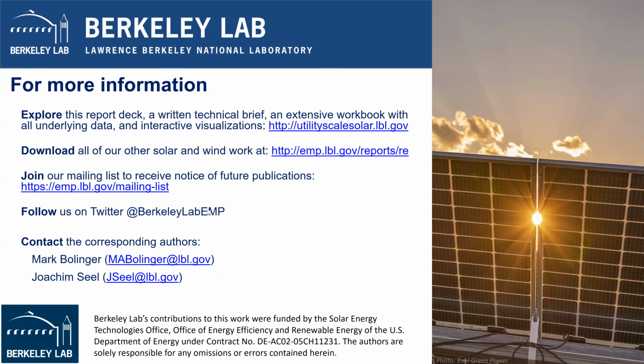Thanks, Mark. There was one question about global horizontal irradiance, or irradiance, and specific yield. So specific yield, I believe, is a metric that describes kilowatt hours produced per kilowatt peak or kilowatt DC. So it's basically just like a metric conversion where you need to put the kilowatt hours per square meter per day into an annual term, and then look at the module efficiency, how much wattage you have per square meter, and then you can transfer those two. But yes, they are directly related.